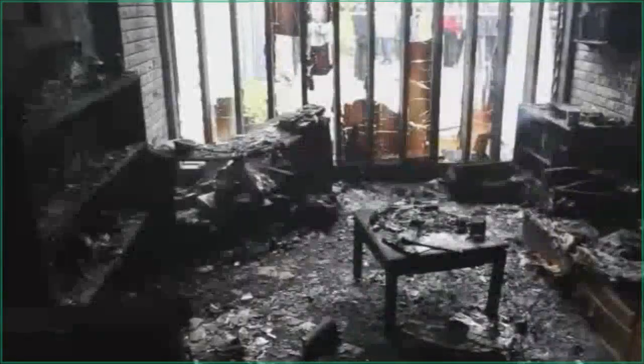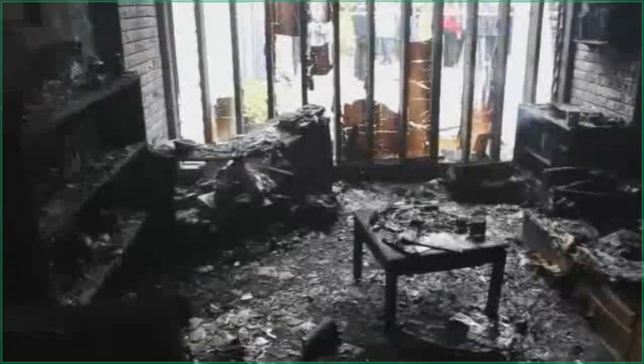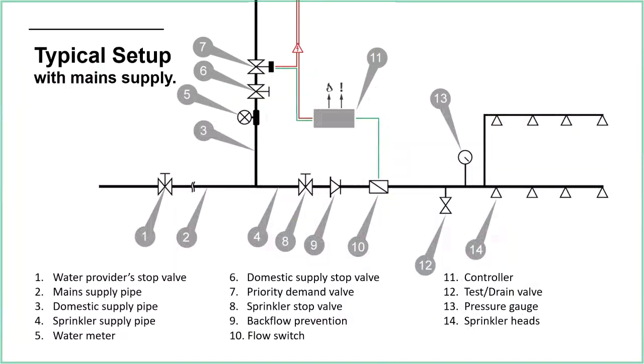Sprinklers in care homes and residential buildings — it's a really powerful message to spread. Let's look at a few system setups. This is a typical setup with a town main supply. The town main comes in from the left into an isolation valve, then branches off — the domestic supply goes one way for toilets, showers, sinks, etc., and the fire sprinkler water goes another. The domestic supply is metered; the sprinkler water is unmetered.